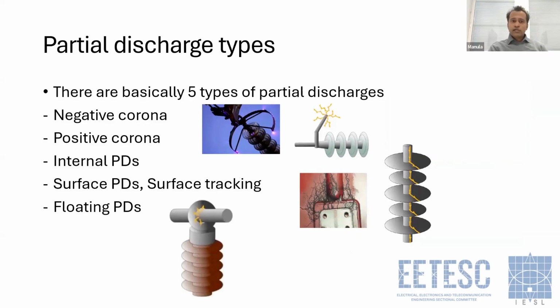There are basically 5 types of partial discharges. The first one is called negative corona. Whether it is negative or positive corona, the corona discharge is a discharge from a high voltage conductor to the atmosphere. We know that the atmosphere has air, and air has a certain breakdown voltage depending on the humidity and environmental factors. Normally it is around 30 kilovolts per centimeter. Whenever the local field stress exceeds this breakdown voltage, a partial discharge would happen in the air. Those partial discharges are called corona discharges.